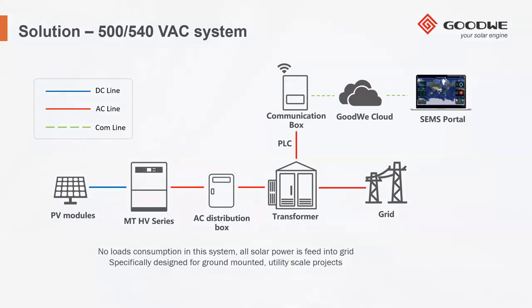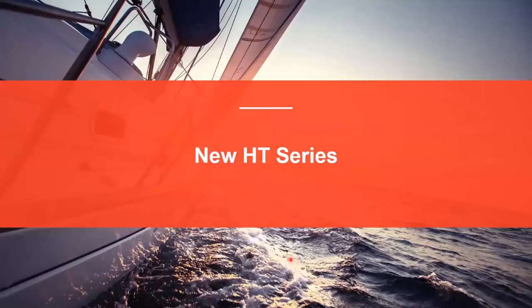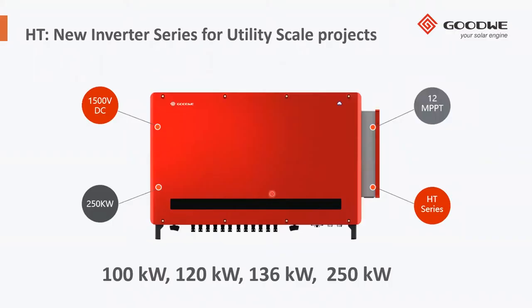The new HT series that we are launching now on the market, this is the picture of the system. It will have 100, 120, 136, and 250 kilowatt. So will be four different power availability. And especially this device at 250 kilowatt will have a 1,500 volt DC input. So this is the version typically designed for large utility scale projects.